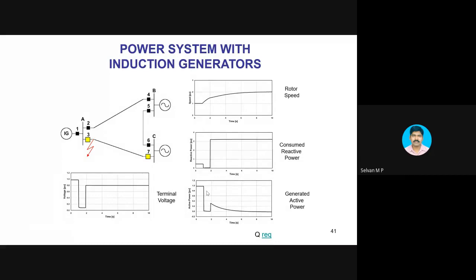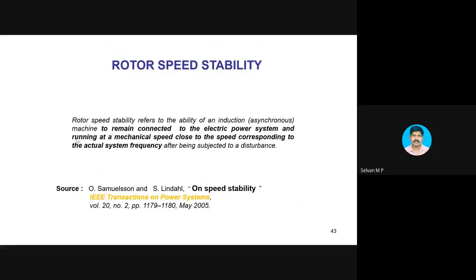So what is to be avoided? We have to avoid the increase in speed, and the machine should not get disconnected from the system. That is what we have to do. That is possible with the help of STATCOM. This phenomenon is called rotor speed stability. It is not rotor angle stability. It is called rotor speed stability.